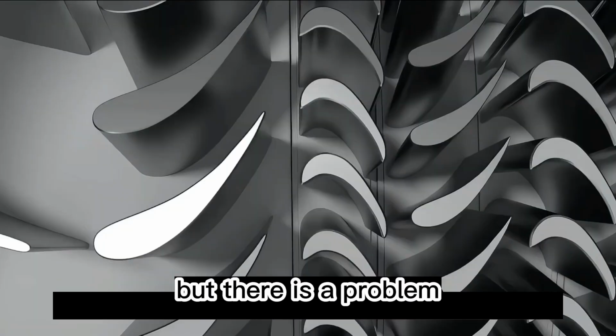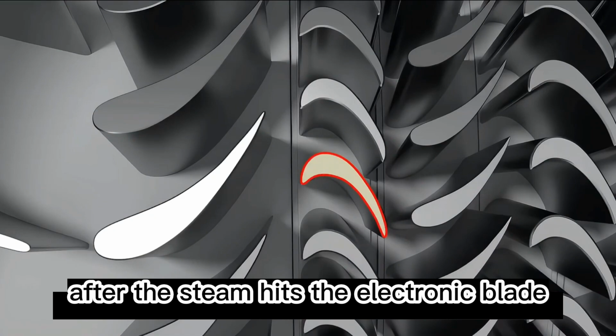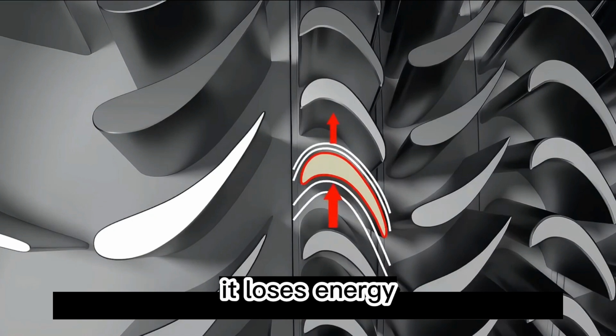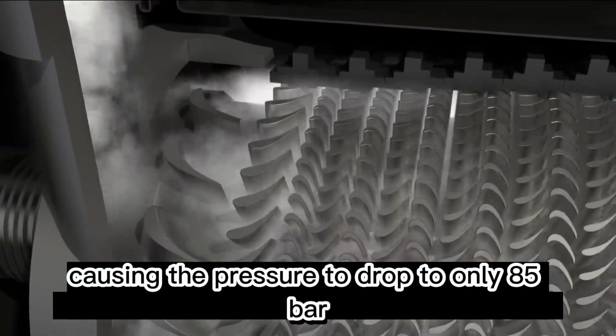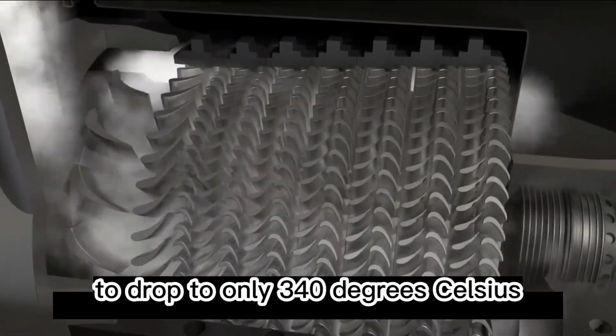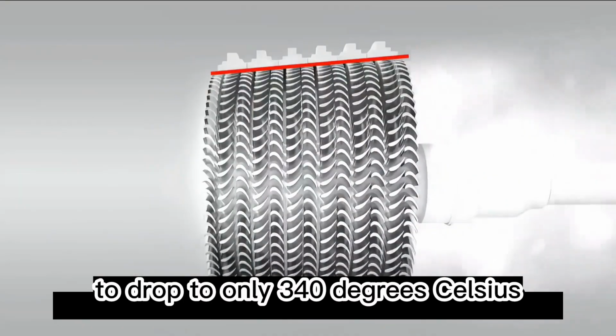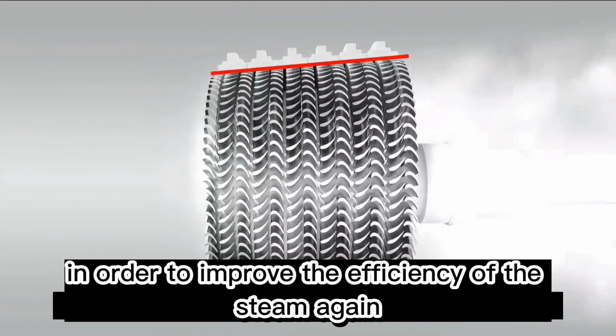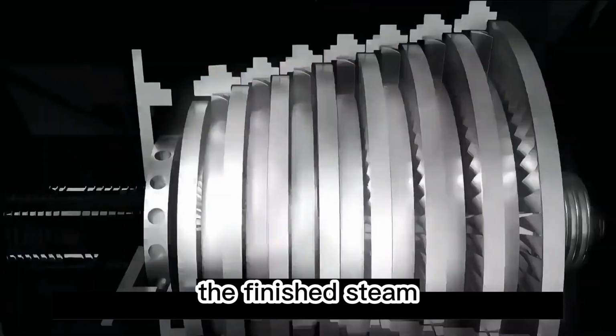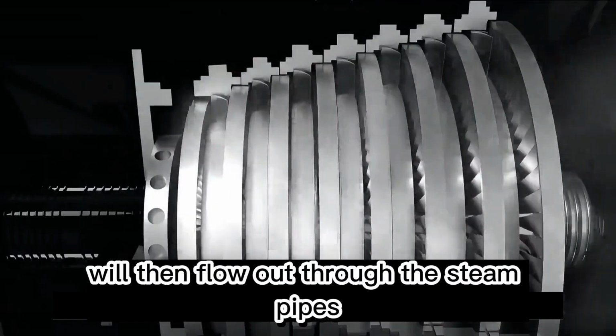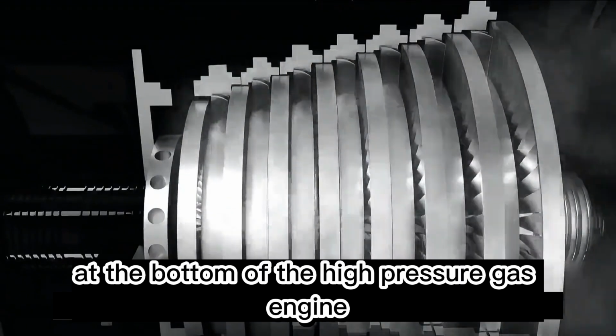But there is a problem. After the steam hits the stator blade, it loses energy, causing the pressure to drop to only 85 bar, and the temperature to drop to only 340 degrees Celsius. Therefore, in order to improve the efficiency of the steam again, the exhausted steam will then flow out through the steam pipes at the bottom of the high-pressure turbine.